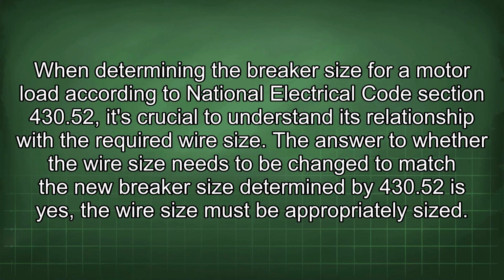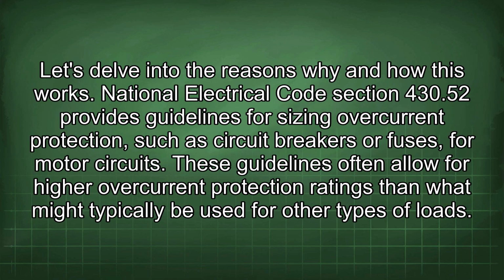When determining the breaker size for a motor load according to National Electrical Code Section 430.52, it's crucial to understand its relationship with the required wire size. The answer to whether the wire size needs to be changed to match the new breaker size determined by 430.52 is yes, the wire size must be appropriately sized. Let's delve into the reasons why and how this works.